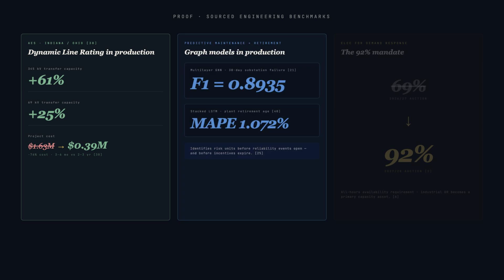The benchmarks are sourced in concrete. AES deployed dynamic line rating across transmission corridors in Indiana and Ohio. Transfer capacity on 345 kilovolt lines rose 61%, on 69 kilovolt lines 25%. The AI and IoT project cost $0.39 million, against an estimated $1.63 million for traditional reconductoring, a 76% cost reduction, deployed in 3 to 6 months instead of 2 to 3 years.